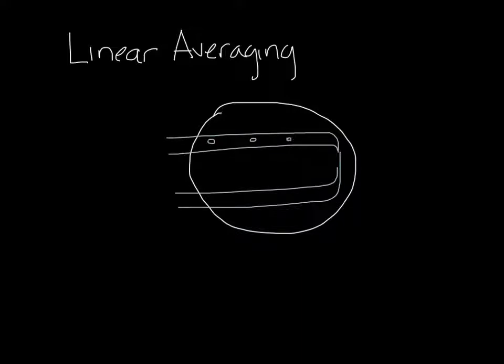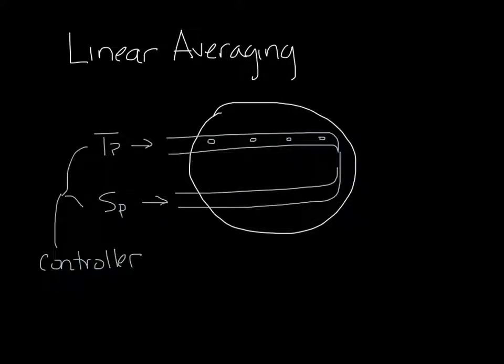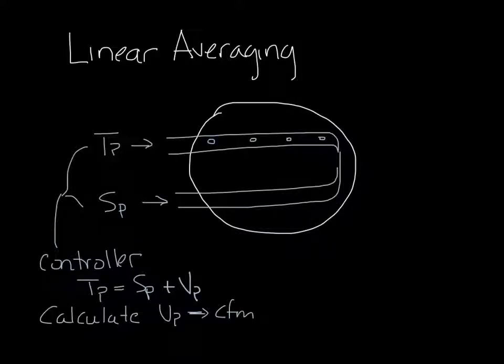The top one would have holes right here and the bottom one would have holes on the back side that you can't see in the drawing. So if you're looking into this flow sensor and the air flow is going in the direction you're looking, the top one would be measuring total pressure and the bottom one would be measuring static pressure. And then both of these are connected back to a controller. Total pressure is static pressure plus velocity pressure, so the controller can use this information from the flow sensor to calculate velocity pressure and therefore velocity and therefore CFM.